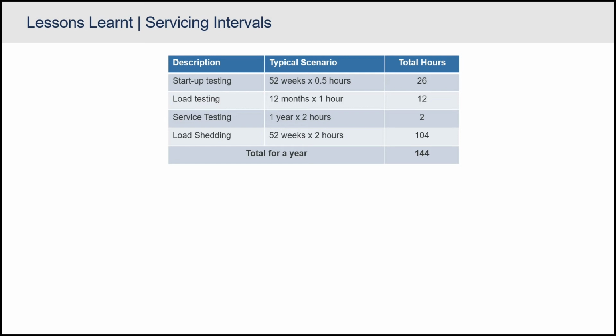If you look at the first table, in that scenario the client tested it every week for half an hour, which is the bad practice I talked about. If we do that once a week for 52 weeks, it equates to 26 hours for a year. If we do proper load testing once a month for an hour, that's another 12 hours.